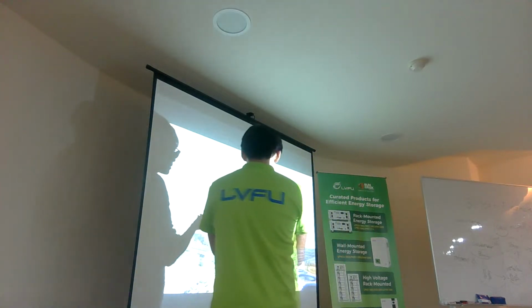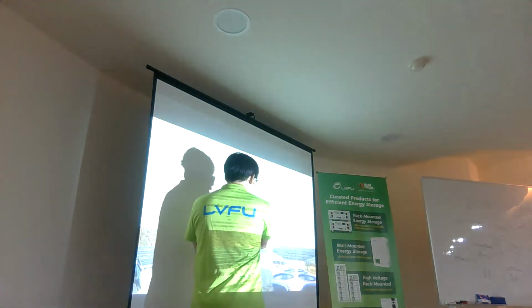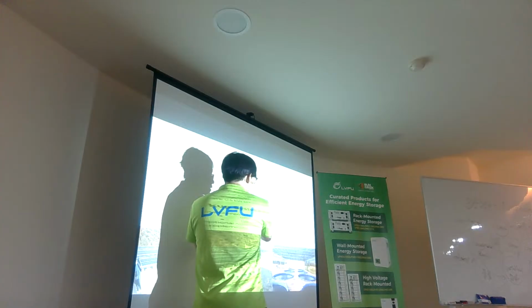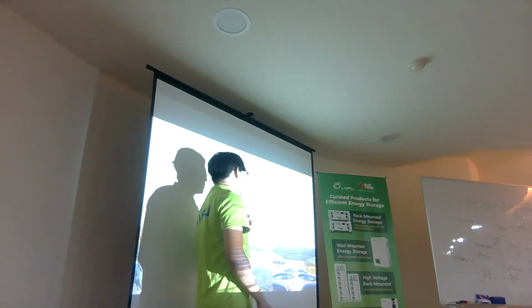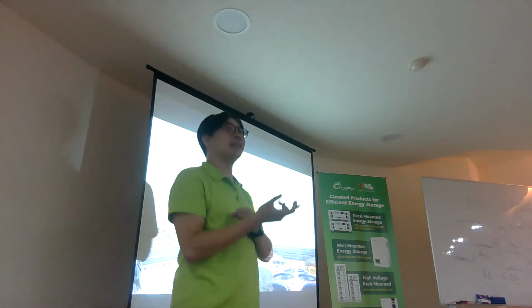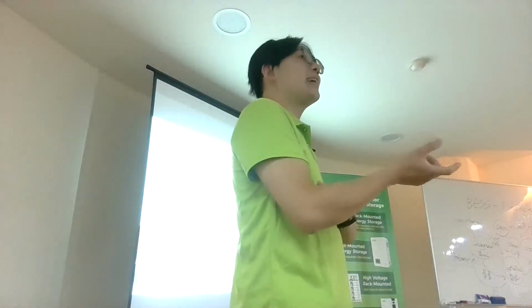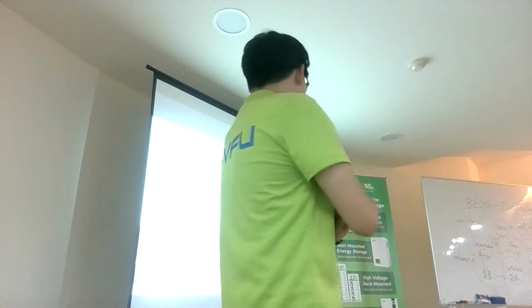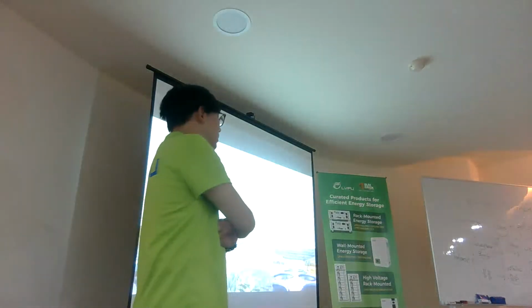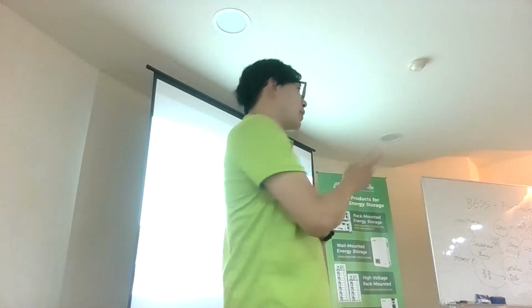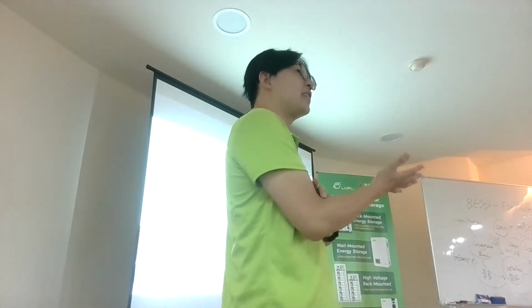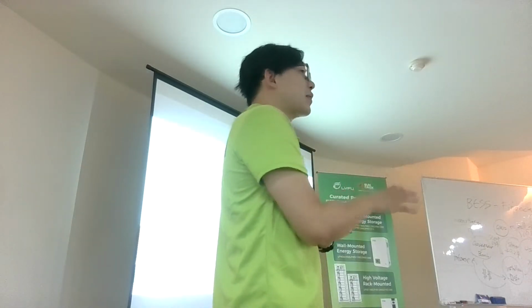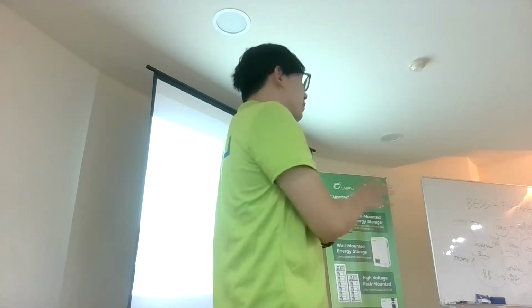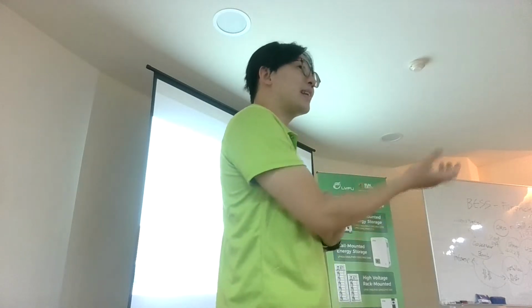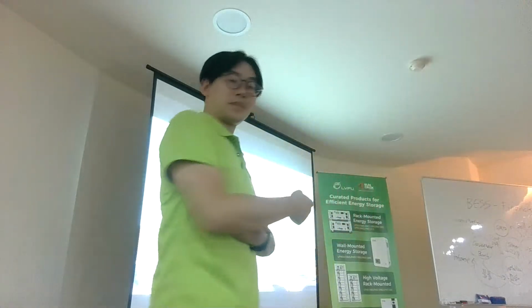Then the BESS begins powering critical loads. This critical load strategy is something you can set in the EMS system, in our cloud. For example, if the power is cut for 2 or 3 days, you can set it so that after 1 day we keep 13% or 15% of energy in the battery, but only release it at low voltage, so it lasts longer than in a normal situation.